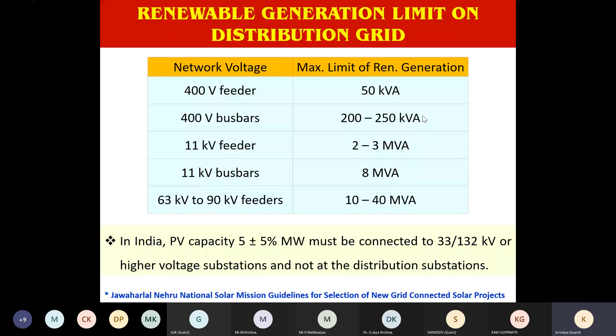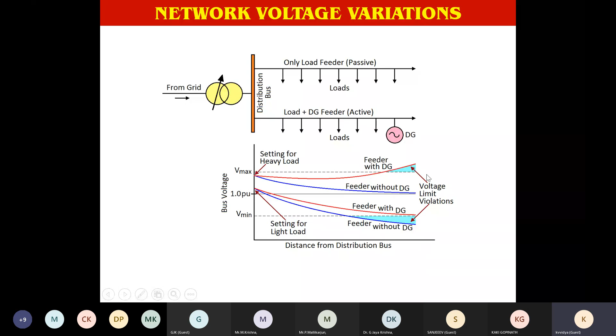Now another impact on the distribution system. We know that in the conventional distribution system, near the distribution transformer, voltage will be relatively high. And as you go away from the distribution transformer, the voltage available will be low because of the line drop. Now, suppose you connect a PV system or wind turbine at the extreme end of the distribution feeder, then that will result in high voltages. Because usually, in order to take care of the voltage drop in the system, the voltage at the distribution transformer will be slightly more than the designated voltage. But because of the DG connection, there will be unwanted overvoltages towards the extreme end. This happened with my house also once. So these are the aspects we have to consider.